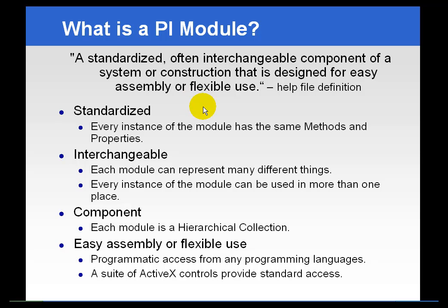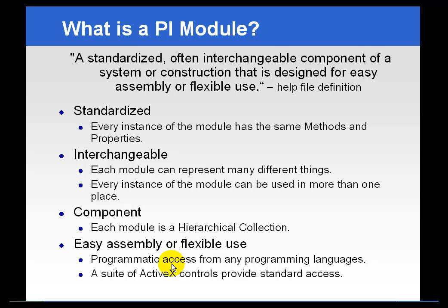Modules themselves are nice because they are standard — there aren't different types of modules, basically just one kind. It has methods and properties, they're interchangeable, and every module can represent different things. You can even use instances of modules in more than one location in the hierarchy. So if you want to set up a view based on equipment, you can do that, and you can also have another view side by side based on process. A module can live in different places and still reference the same tags or points. Each module is a component in a hierarchical collection, meaning users can click and drill down through that hierarchy. We also provide programmatic access to the module database, so if somebody wants to use it programmatically — similar to the way ACE does — they can do that.